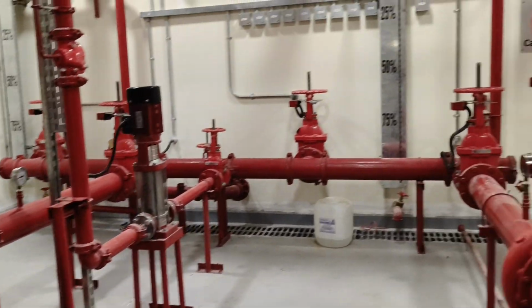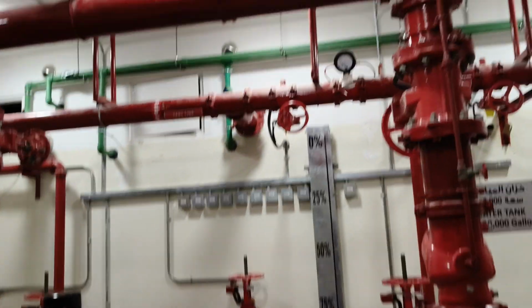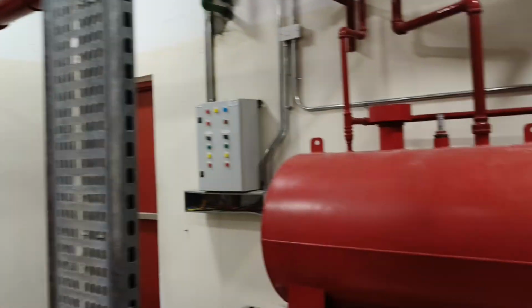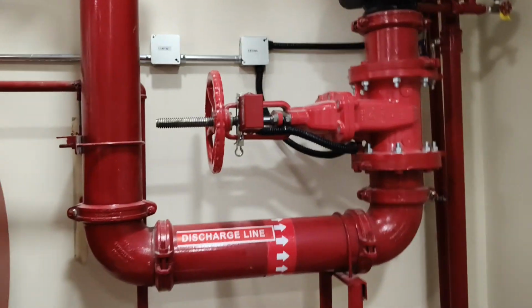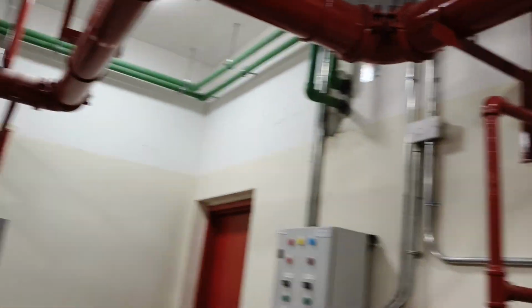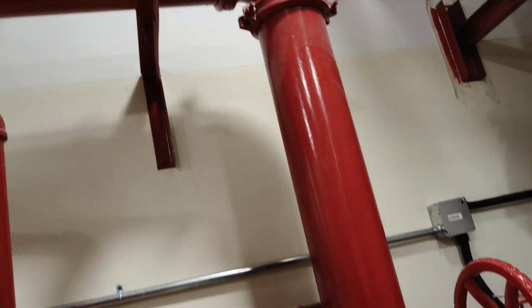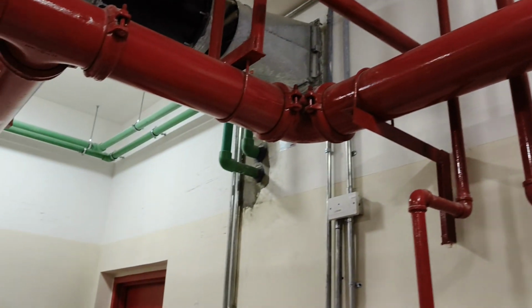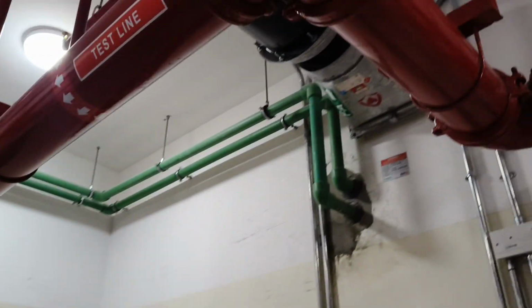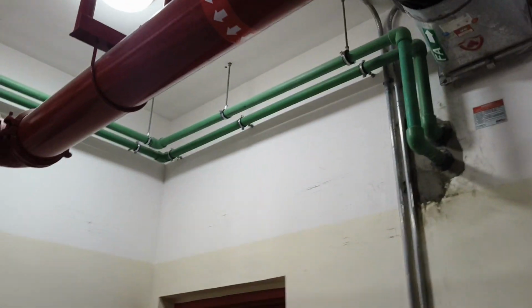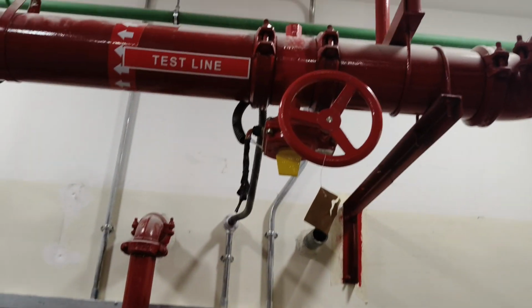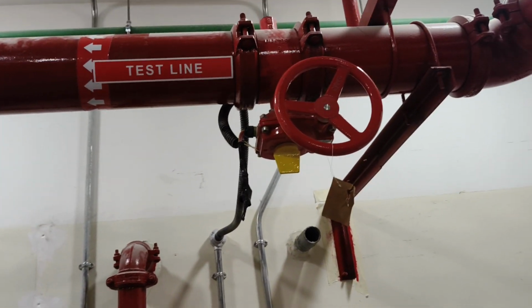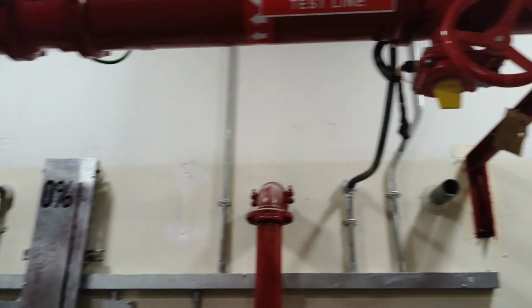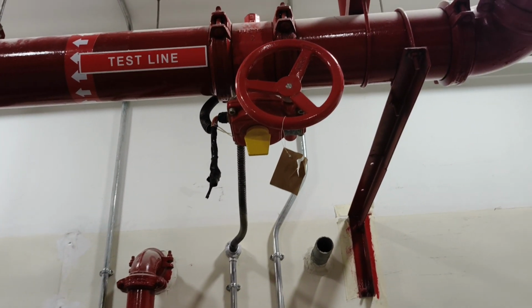So during testing, if you would want to do the flow test, what you have to do is close the main discharge valve. If water comes from here and comes up to this side, and it meets this closed valve, then the water will definitely have its priority passing through the test line. So this is the throttle, the bypass valve, and the throttle valve. All have to be in a normally closed condition.